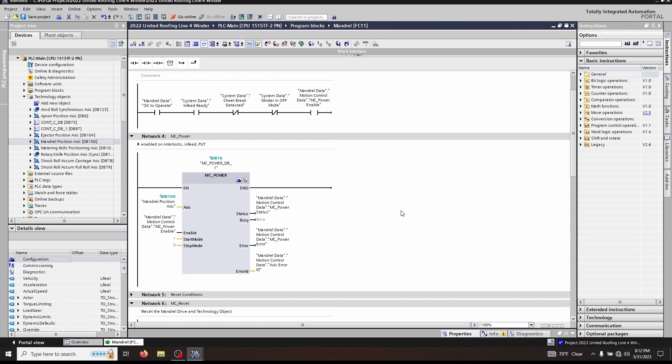On a Siemens S120 or a G120, you will know that the drive is enabled because you will hear the cooling fan turn on. So let's take a look at the actual function block's inputs and outputs.